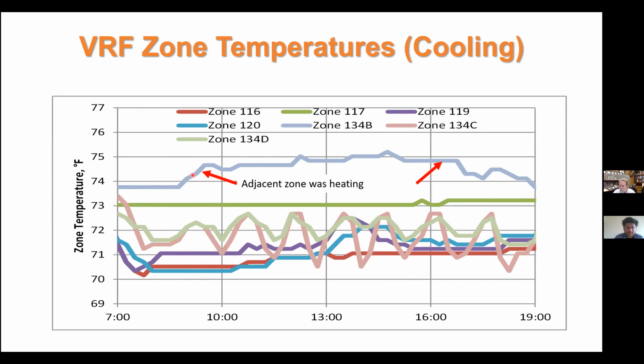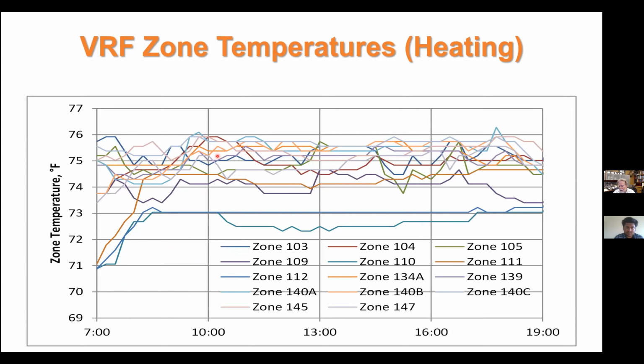Here's a case where we were cooling one zone, and the zone next to it was heating at the same time. And these are in an open plan office, so they're exchanging cold air and hot air. And so we see these units are cooling, these units are heating, and they just run all the time. So I'd say that's a lot of the cause of the differences in electricity consumption. But we are going to set that aside and say, okay, if the cooling and heating was really needed to maintain comfort, what's the system performance like? So we set this control strategy aside when we get to the system performance.